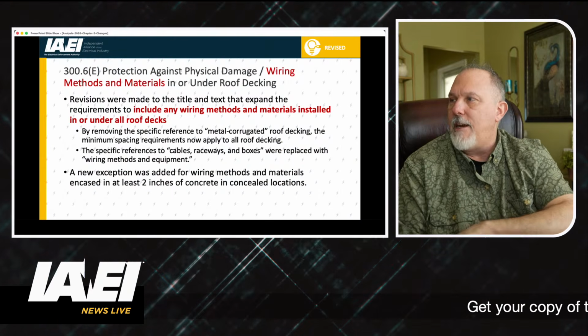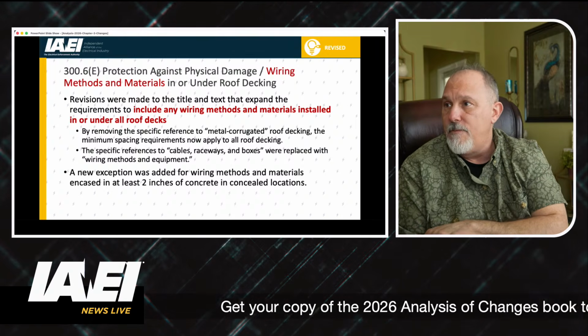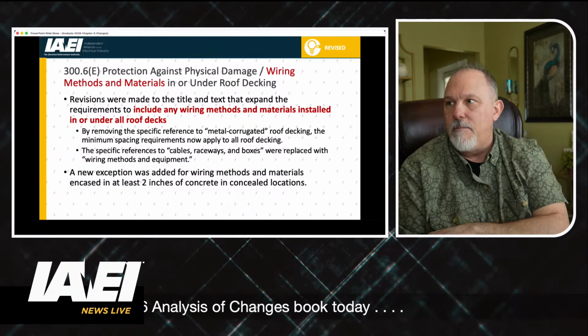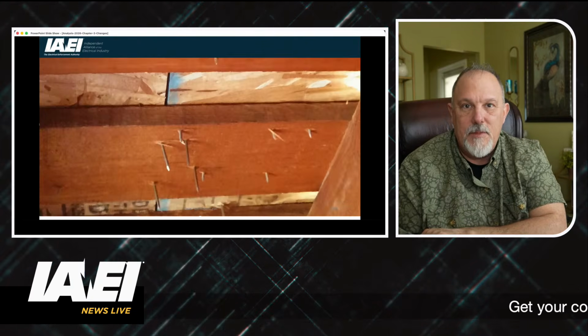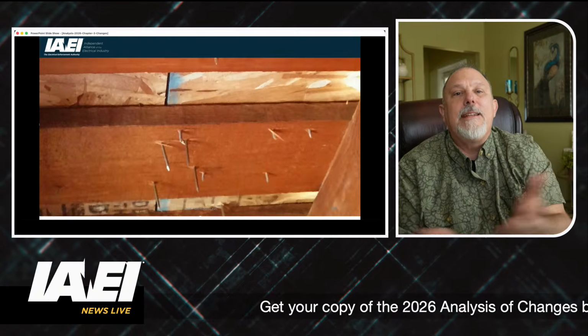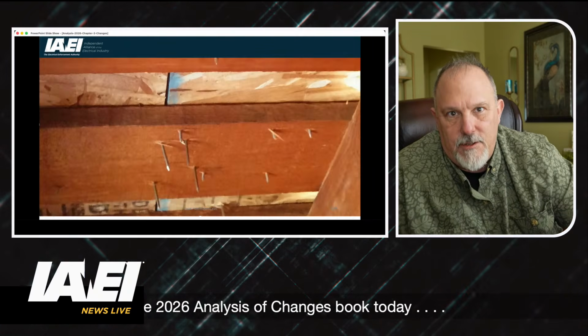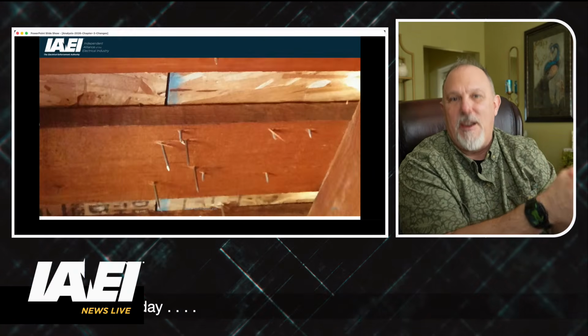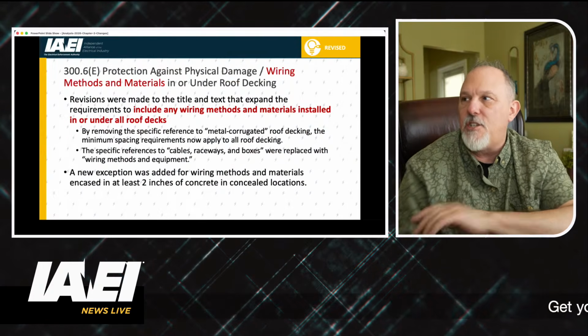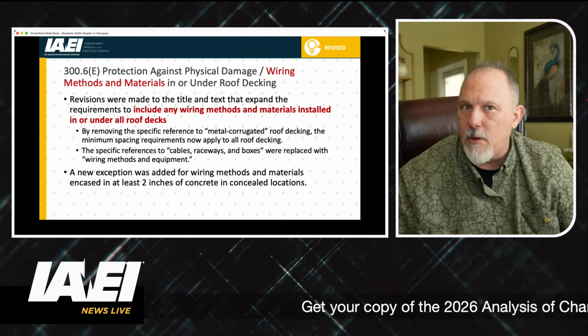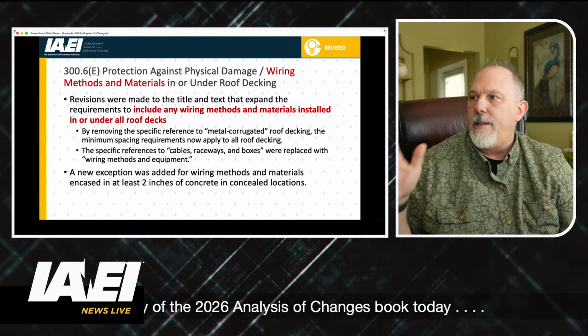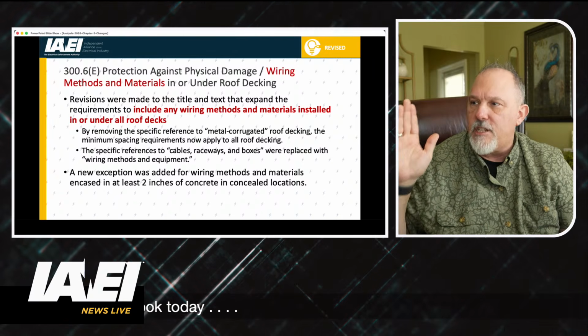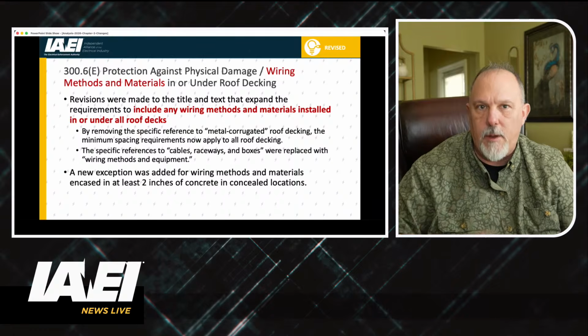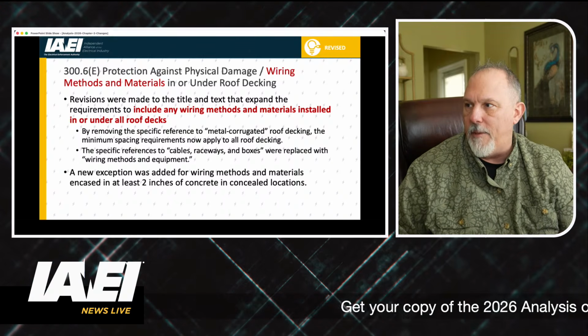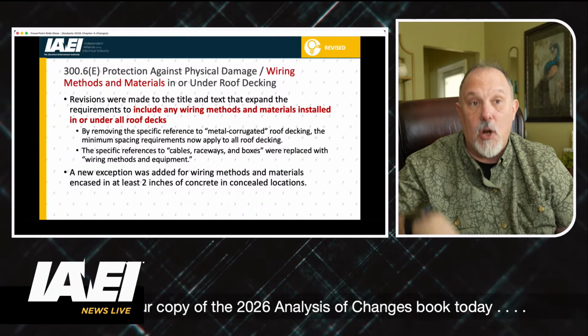Well, this section in 300.6 recognizes that, look, it doesn't have to just be the metal corrugated roof decking. I can have a wooden roof decking that presents the same hazard. So why pick on one construction method when other construction methods have the same issue? So they removed that metal corrugated reference, and it's not just cables, raceways, and boxes, but they just said wiring methods and equipment, because it's any wiring method and equipment.